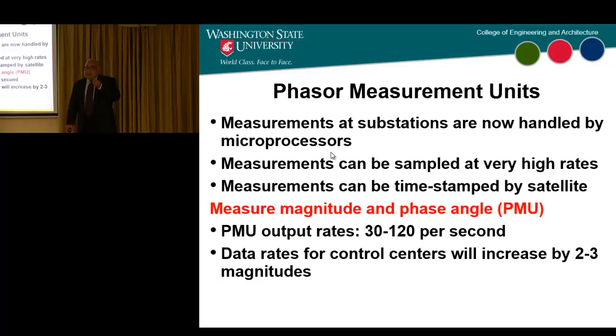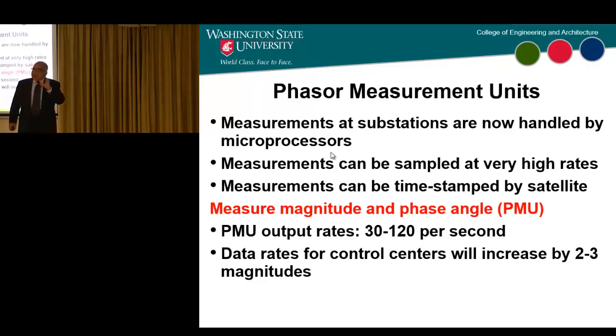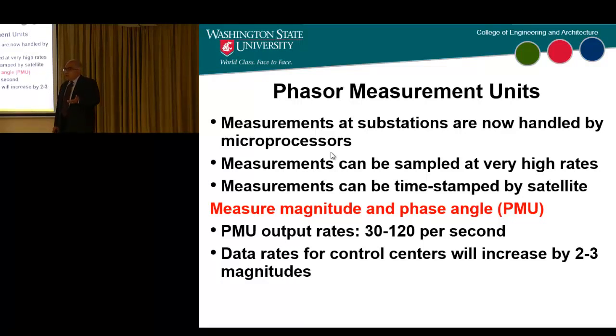But now, because of the GPS connection, the other thing that has happened is you can measure much more rapidly. In the old days, because of the microwave channels we started using in the 60s, we could only get data at very low baud rates—every 2 seconds, every 4 seconds. Now we're talking about measuring 30 times a second, 60 times a second, at very fast rates. The sampling in the PMUs is done at much higher frequency, but the output data we're getting is about 30 to 120 times a second. So the data rates are much higher coming into the control center.